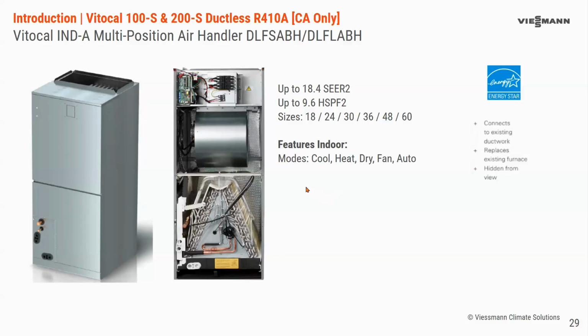So, features of the indoor unit, same modes. This has multi-position, so four-way installation: upflow, downflow, left or right. As I mentioned, there is some caveat to the compatibility. Multi-zones cap out at 36,000 BTU, regardless of the outdoor unit capacity. You can only have as large as a 36,000 BTU air handler on a multi-zone, and you can only have up to 2 air handlers maximum. So if you require larger BTUs, that's when you'll look at a ducted application.